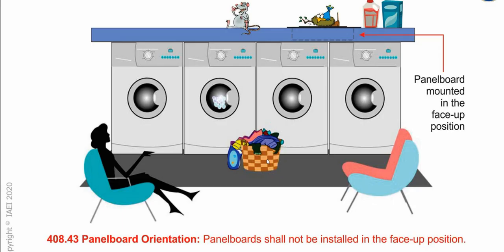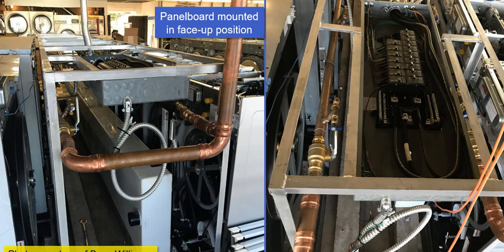So here is kind of an example, and I've got a picture here following that shows mounting a panel face up. Obviously this is in a laundromat. Check this out. This is a laundromat where you have a row with the washers on this side and the dryers on that side, and then you have this framed system that is probably pre-manufactured for laundromats running down the middle.